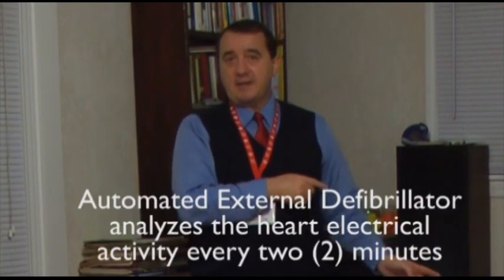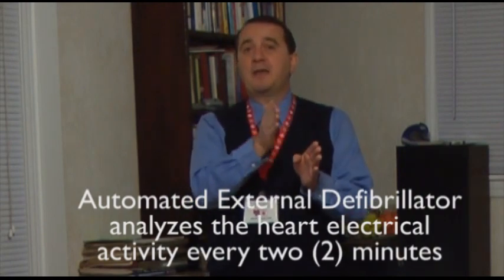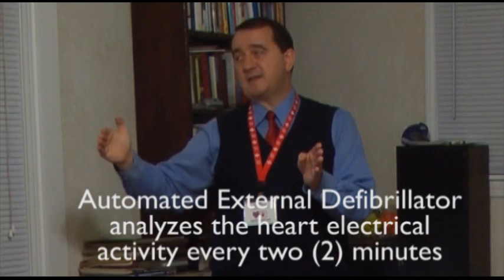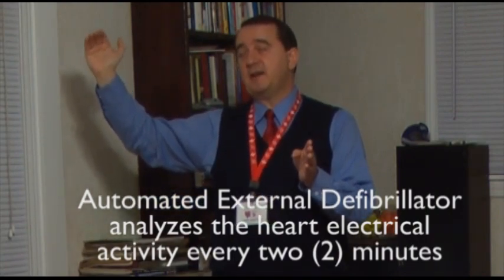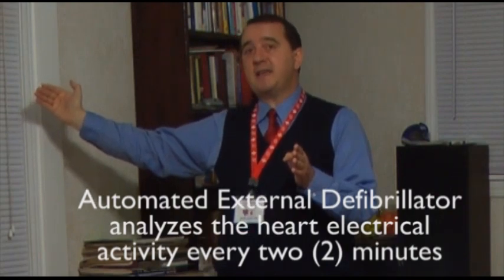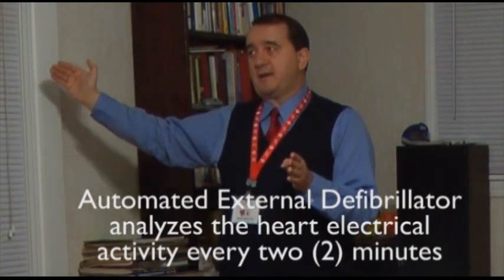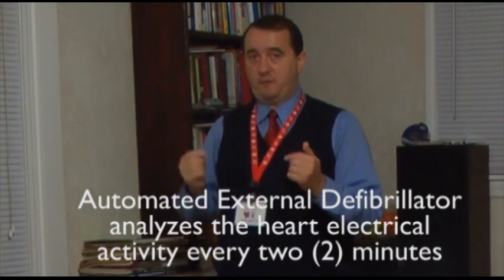Sometimes one shock is enough, sometimes it's not enough. The machine is designed to analyze every 2 minutes. 2 minutes later, it's going to analyze and decide if an electric shock is necessary. Then 2 minutes later, it's going to analyze again and decide if an electric shock is necessary or not. And then 2 minutes after that, it's going to analyze again, and so forth. Remember, we said one of the moments when we need to stop the CPR is when the AED is analyzing. It is important: when it analyzes, we do not touch the person. It's important for the machine to decide based on the person if an electric shock is necessary or not. If the heart has no electricity at all, an electric shock probably will not help, but we still need to use the machine.